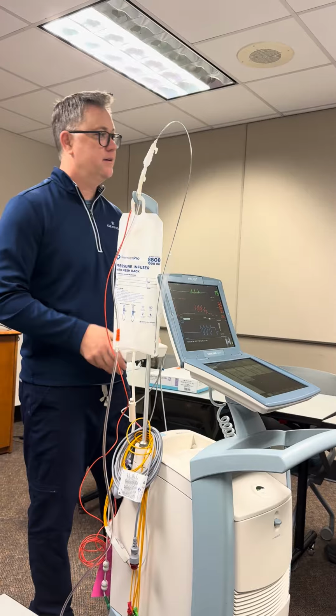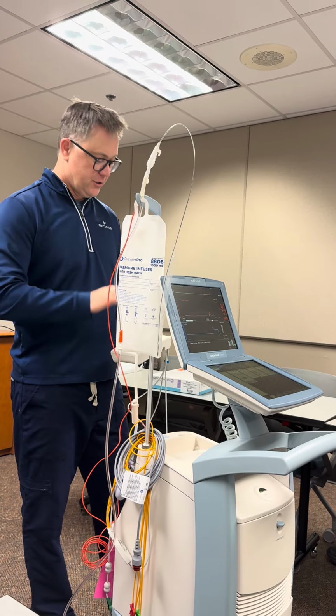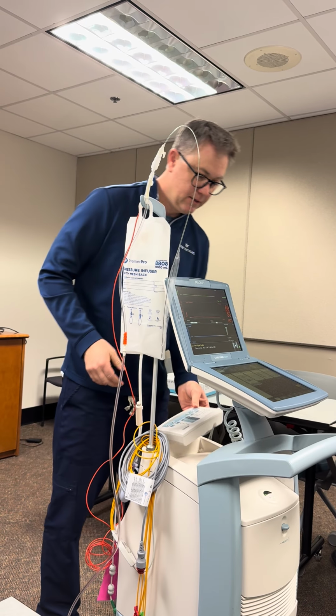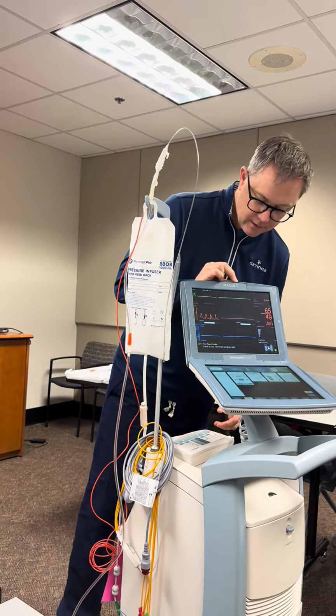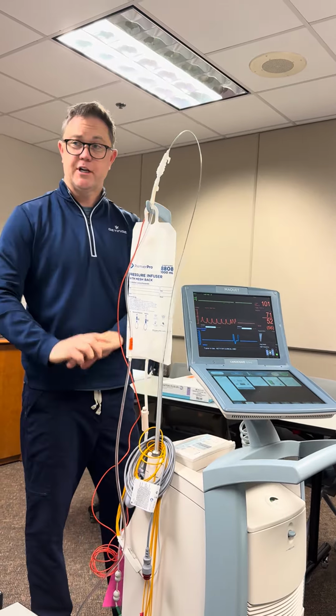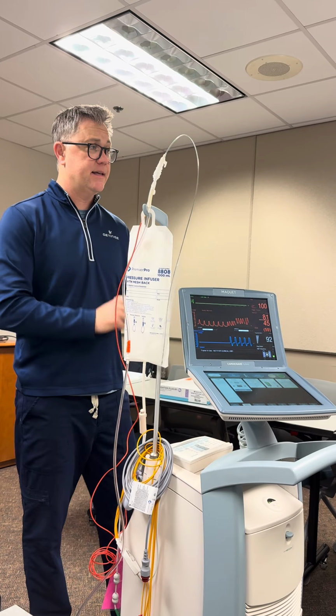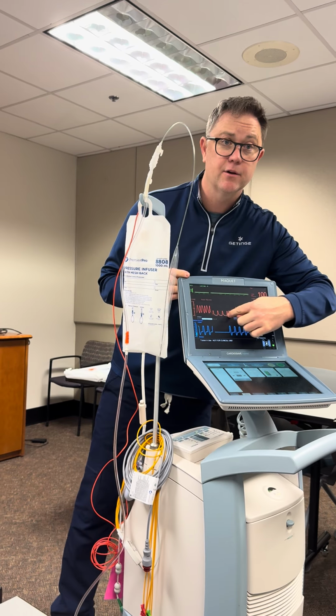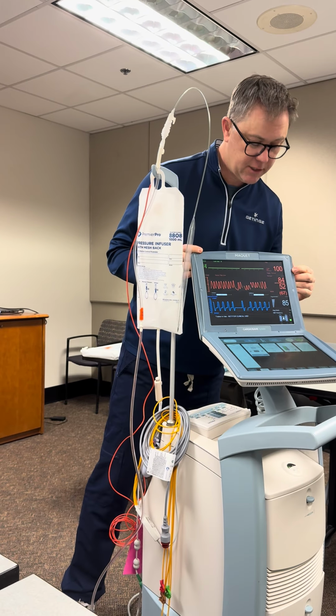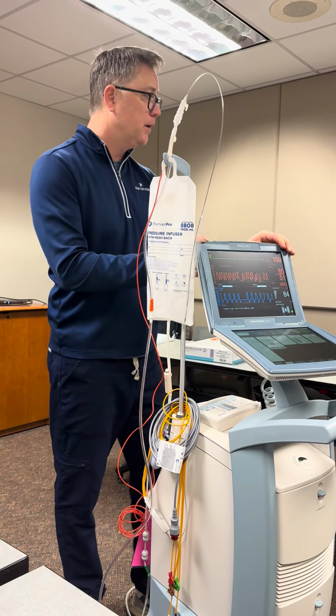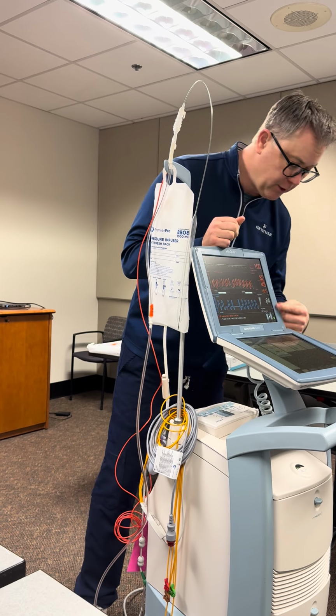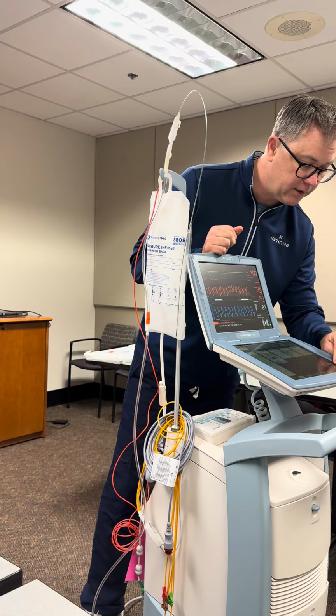This one, so you start your chest compressions. Once you start those chest compressions, the balloon pump should recognize that as a pressure trigger and augment those chest compressions. So just be aware of that. You don't need to do anything to the balloon pump. It's going to alarm at you because our augmentation alarm is going to fall here and all those things.